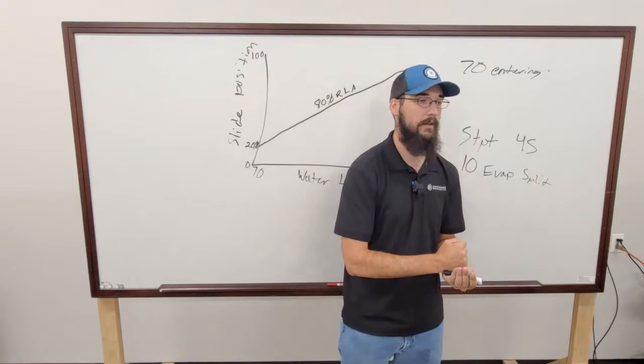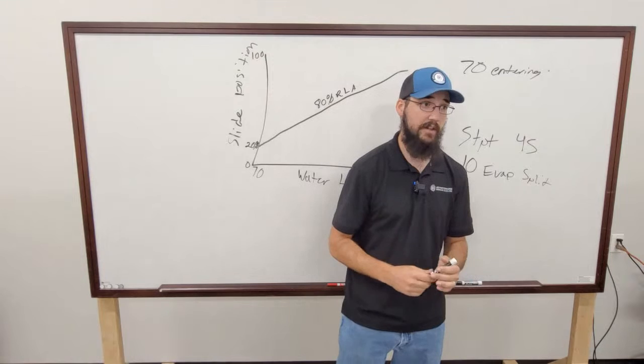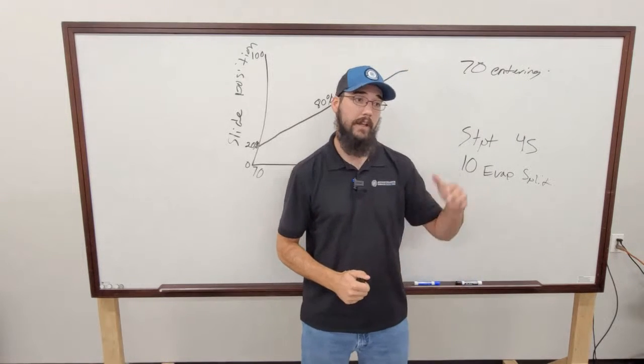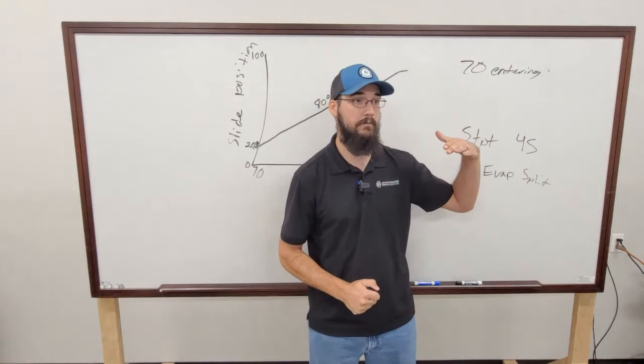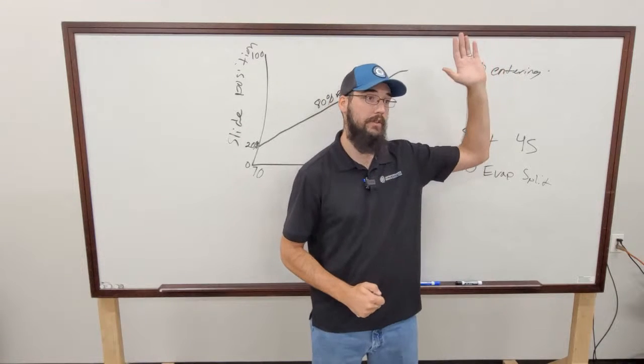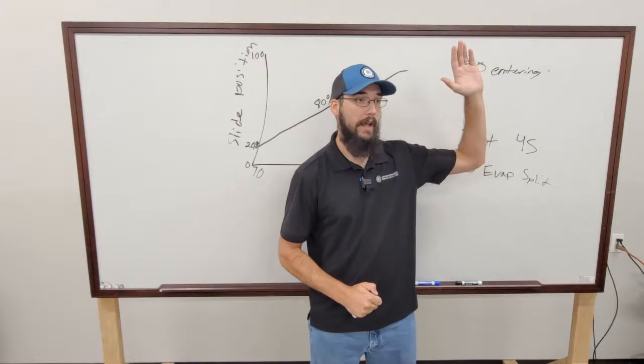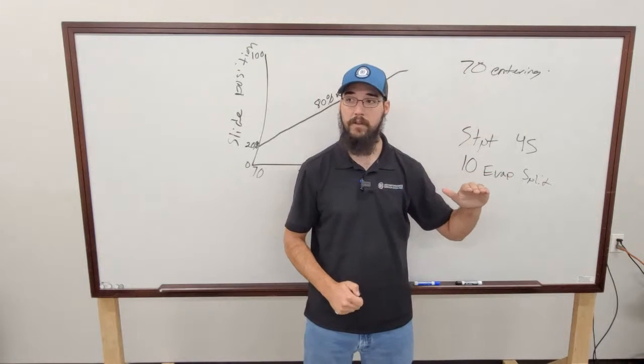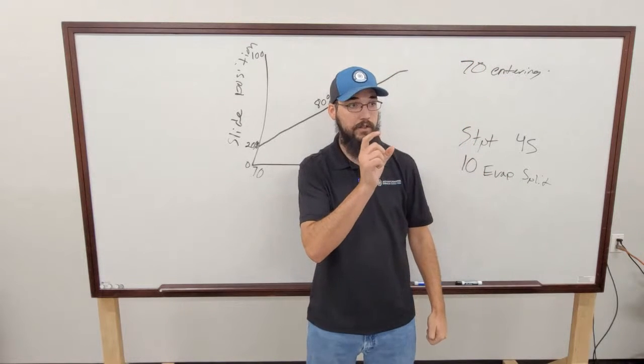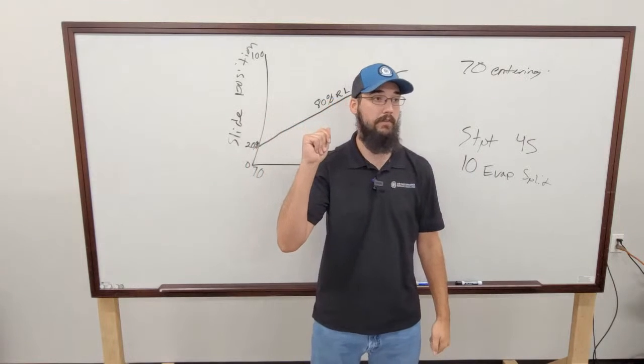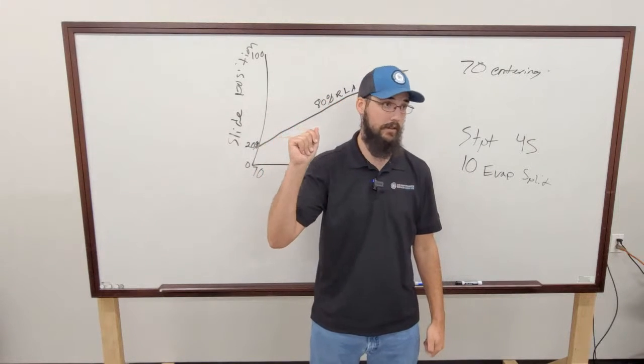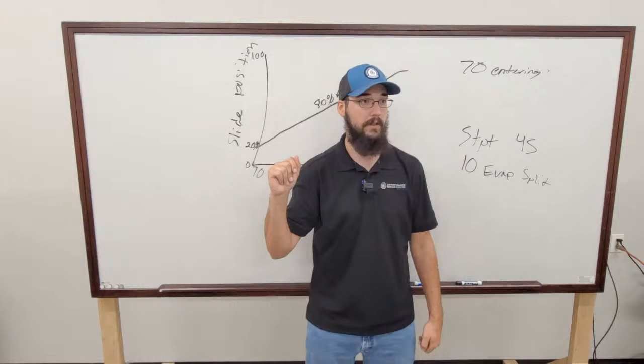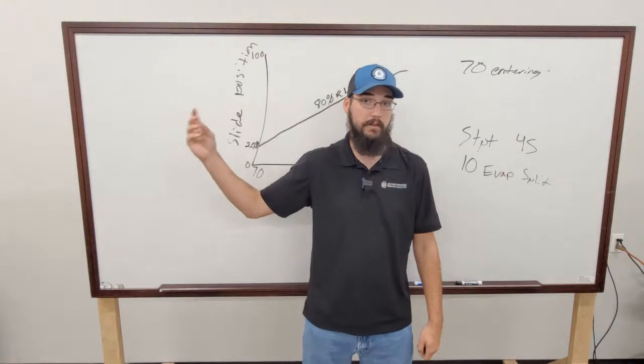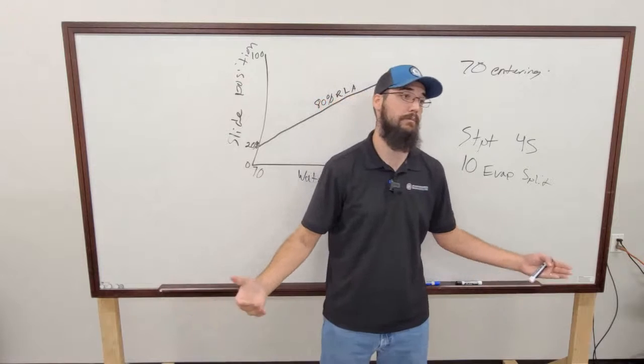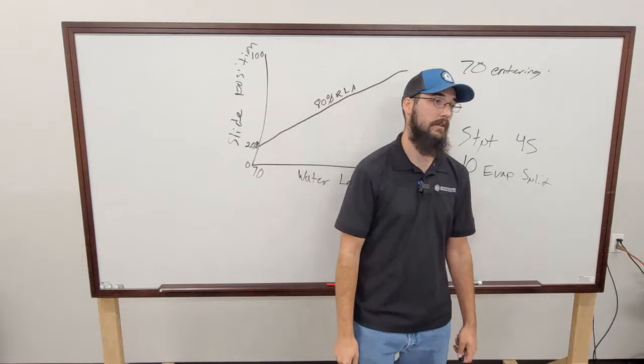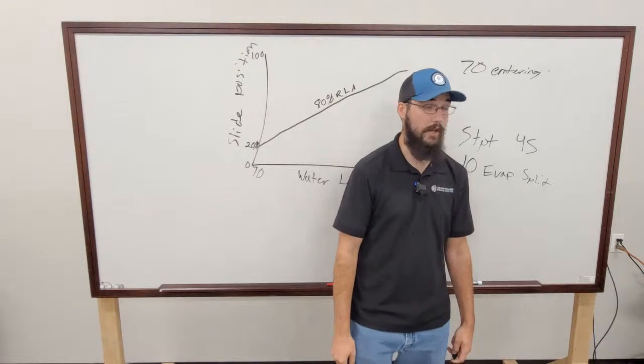And I had this exact scenario on a centrifugal recently. It didn't have a current limit programmed. It was defaulted to 100%. And during a heavy pull down, it had enough fluctuation that all it takes is to trigger that safety. That's all it's looking for. You tap it, it's going to shut down to protect that system. It would tap that safety and shut it down before it ever got to process the loop down. Yeah, slow and steady wins the race. Yes, absolutely. Slow and steady.